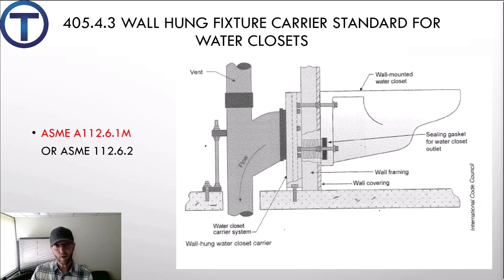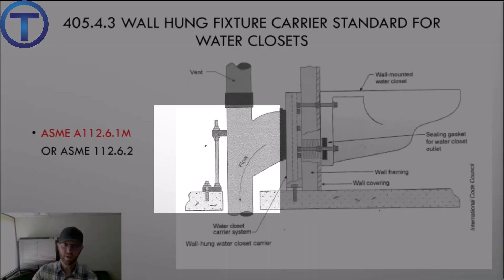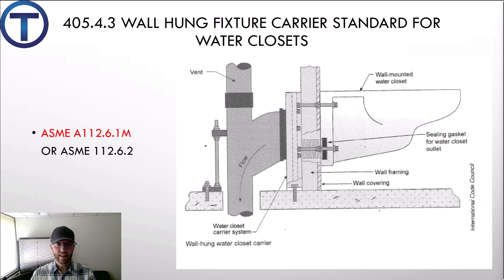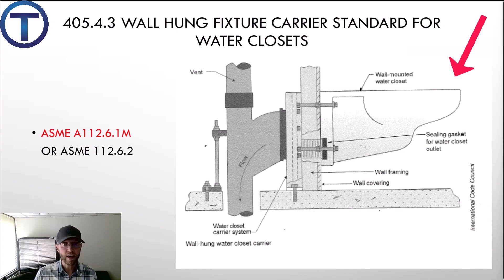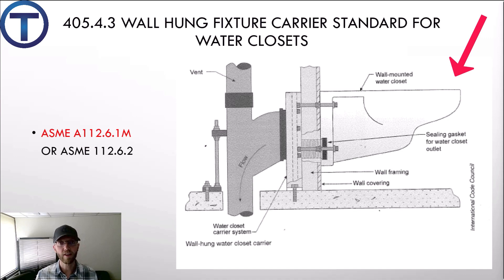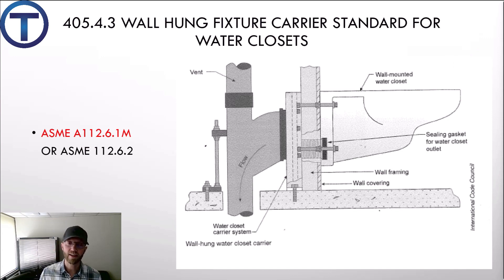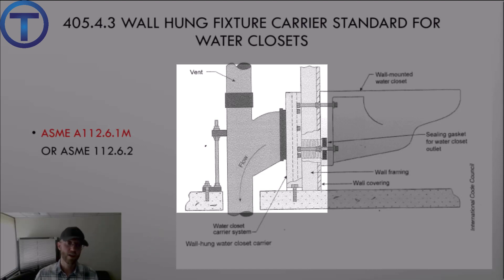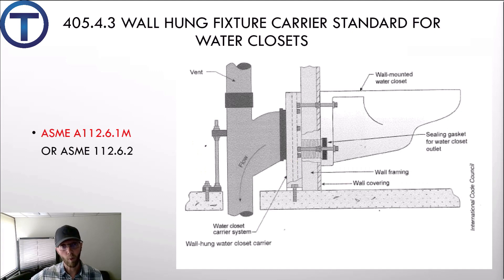There's also a single carrier option — when doing a single carrier inside a wall, you have to have extra support with a bolt and anchor on the back side. Think about it: this is a lever. The person sits out on the rim of the bowl. The toilet weighs about 70 pounds, add water and you're near 100 pounds, then put a human on it — potentially 200-plus pounds. We're talking 300 pounds hanging out there. That's why inside the wall the carriers must have very secure anchors into the floor and concrete to support all that weight.